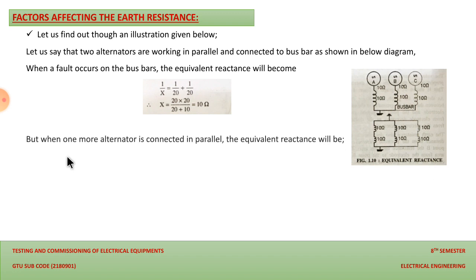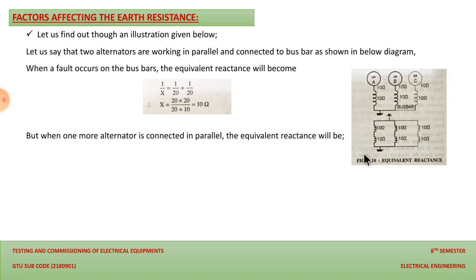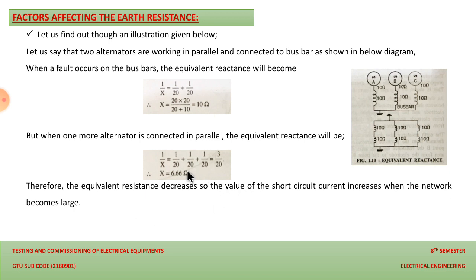When more alternators are connected, these three alternators in parallel, the equivalent reactance will be 1 upon X is equal to 1 upon 20 plus 1 upon 20 plus 1 upon 20. Comparing the reactance of the system, for two alternators the reactance is 10 ohm, and for three alternators the reactance is reduced from 10 ohm to 6.66 ohms. So the equivalent resistance decreases, and the value of the short circuit current increases when the network becomes large. If the system is large, then the short circuit current is high, as we discussed in the previous slide. This is the proof that the short circuit current increases as the system is large.